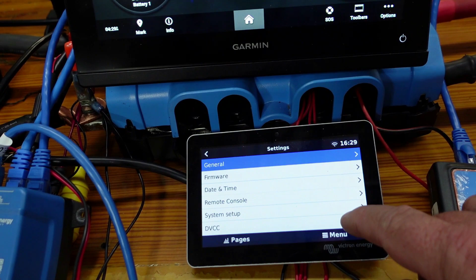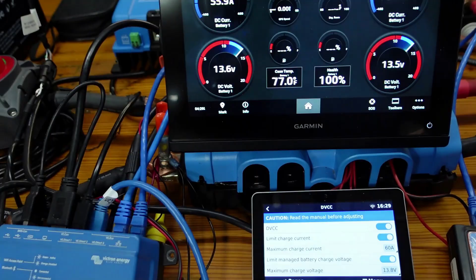Let's go back into the settings, DVCC. Again, this maximum charge current and maximum charge voltage - how that might be used with these Epoch batteries and the Victron V2 CAN bus protocol. In these batteries and in the V2 CAN bus protocol from Victron, they have pre-warnings and warnings. These batteries also have recommended charge voltages and charge currents - I think it's actually 14.6 or 14.4 for these batteries.